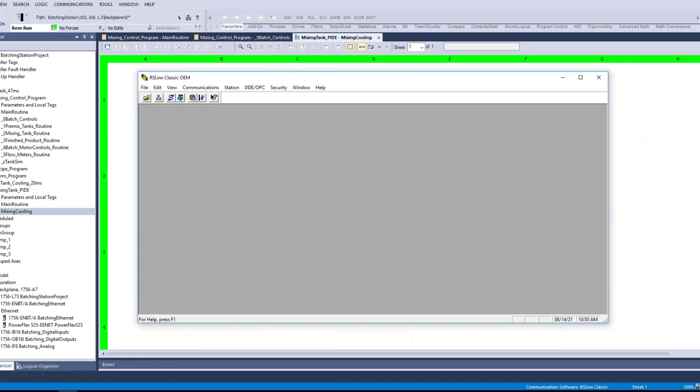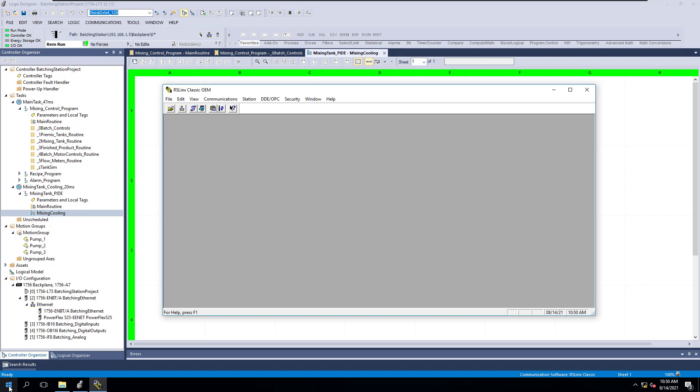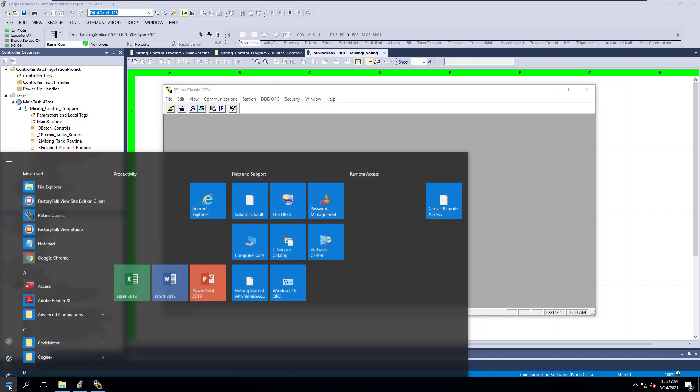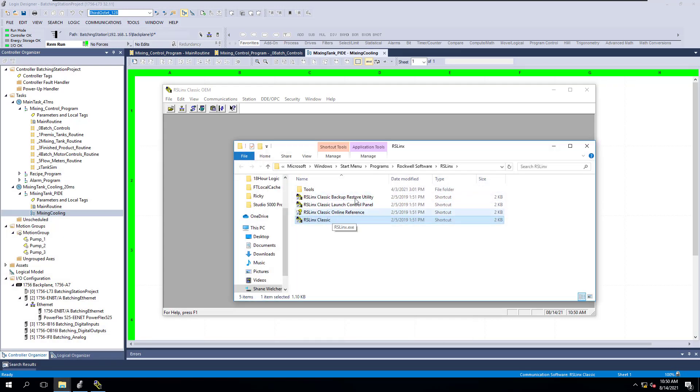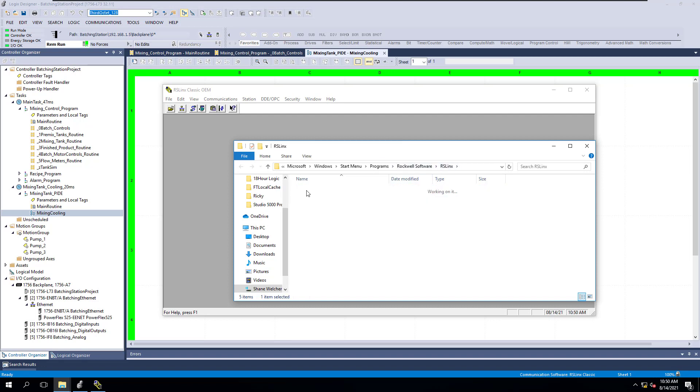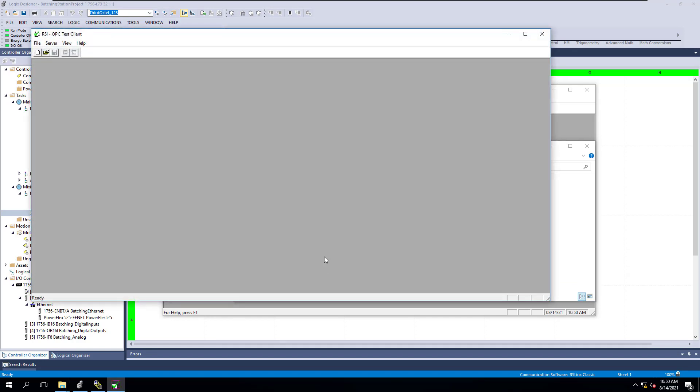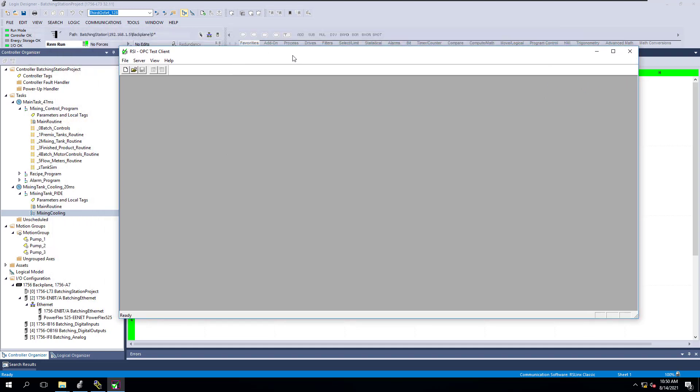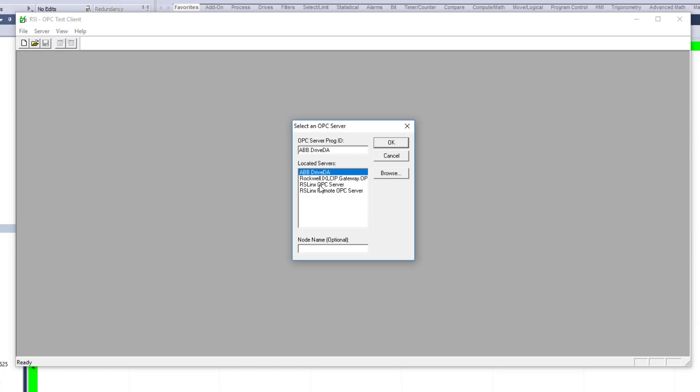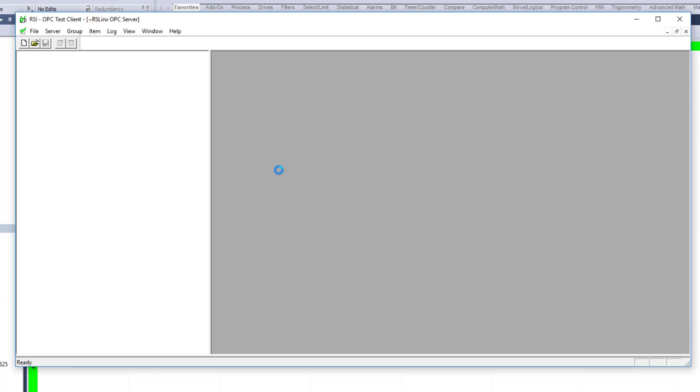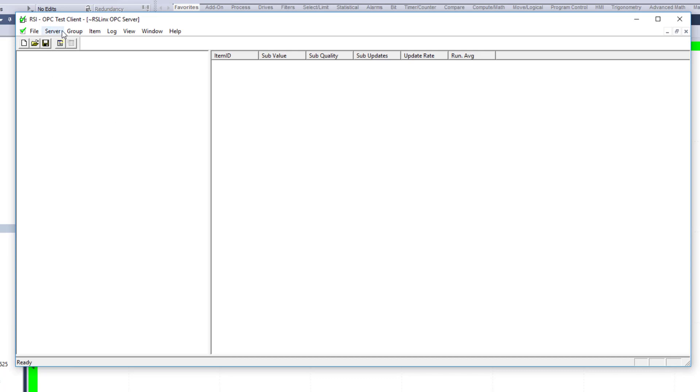Now at this point, you want to go back to your actual software. You can come over here and right-click. If you're on Windows 10, it's sometimes easier to right-click and go Open Destination, this way it throws you in where RSLinx is. Then you're going to go into the tools, and you're going to go to OPC Test. So this is the OPC Test Client. All you're going to do is basically connect, you can connect your server. At this point, you want to do an RSLinx OPC Server. You can do remote if you're doing remote. In this case, we're doing local. So then that's connected.